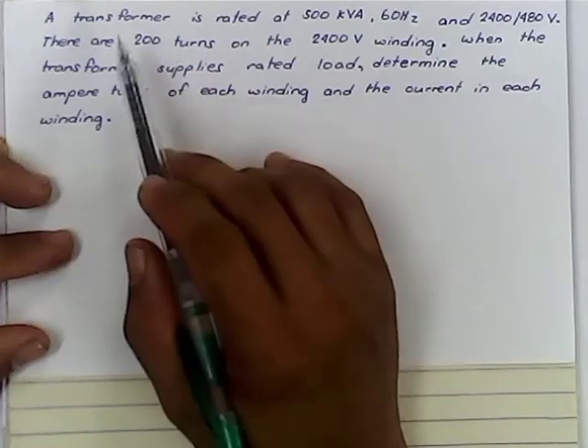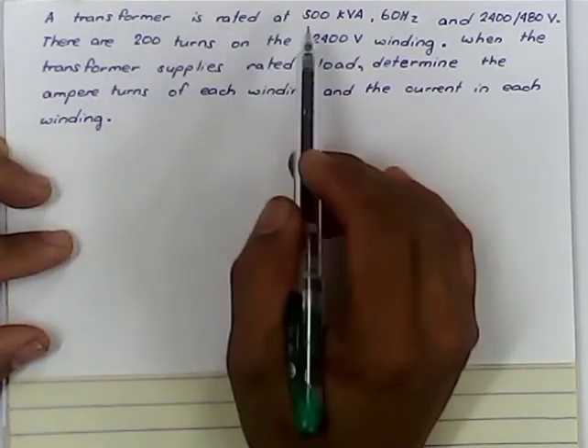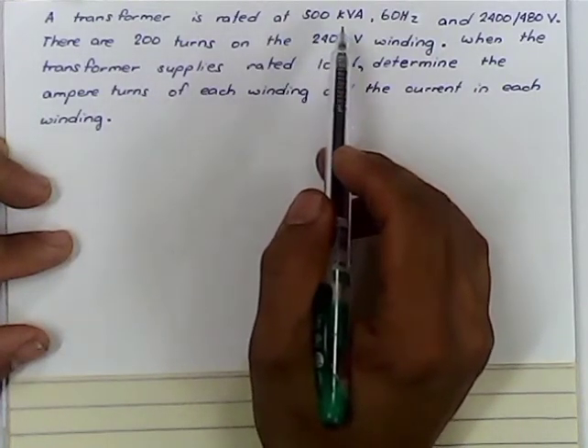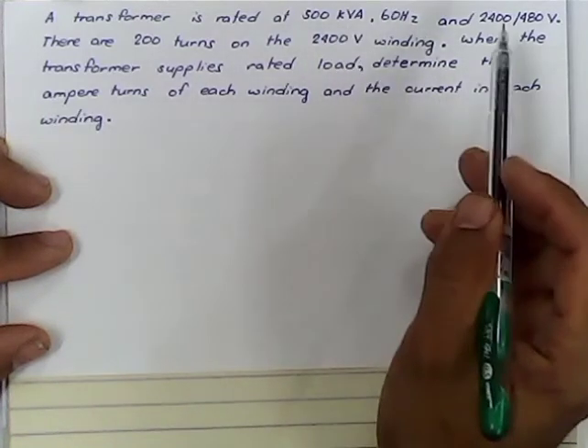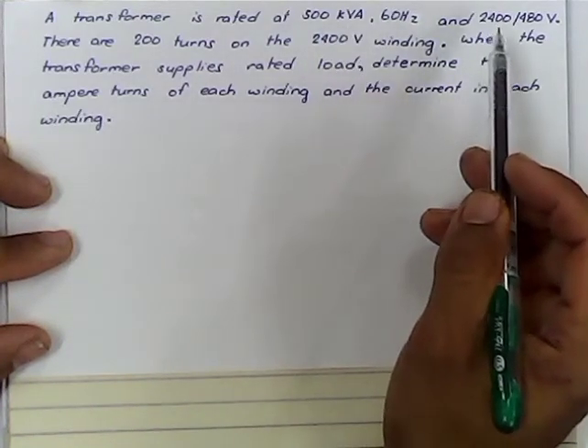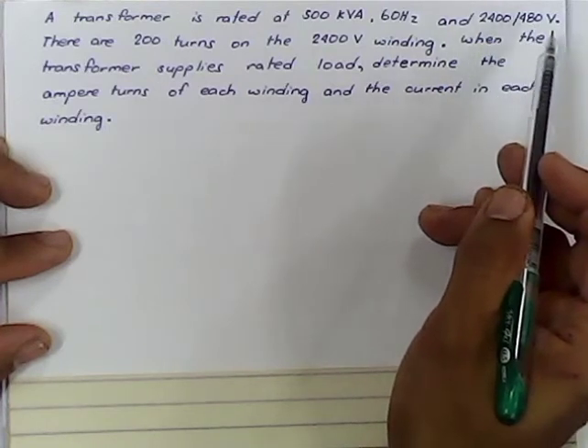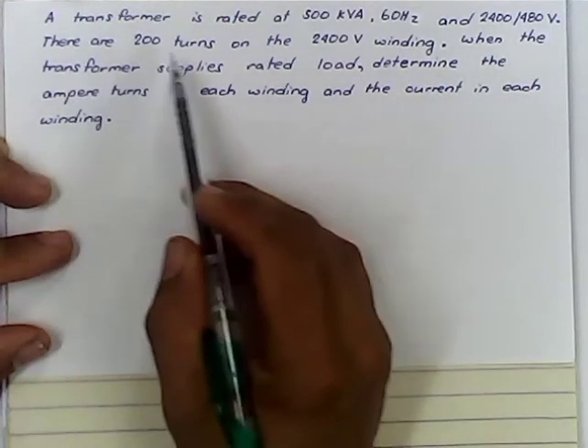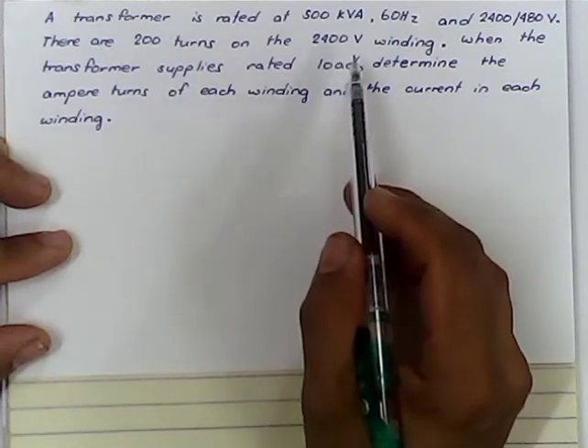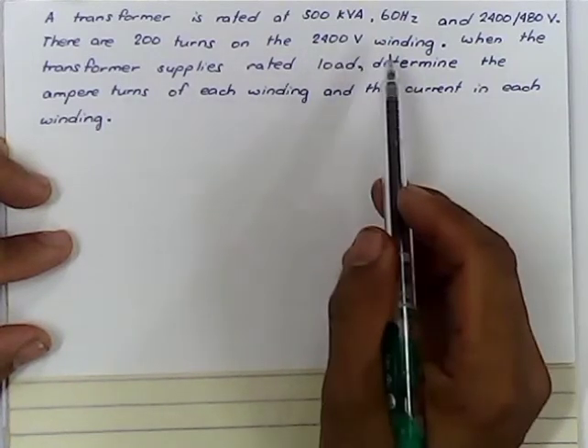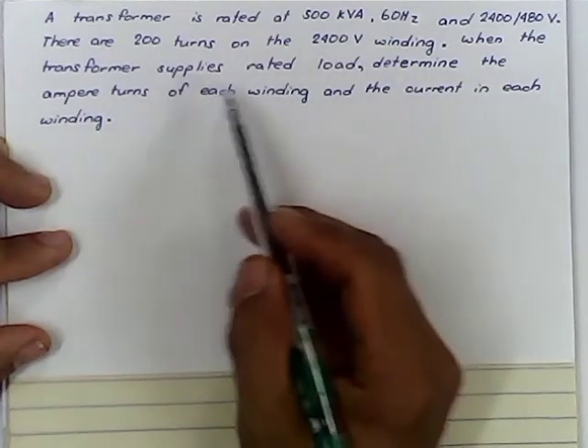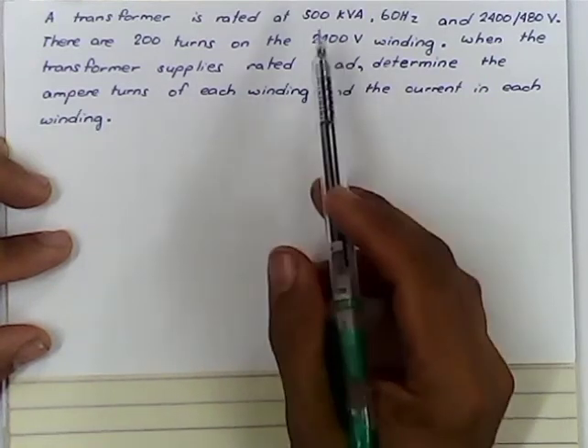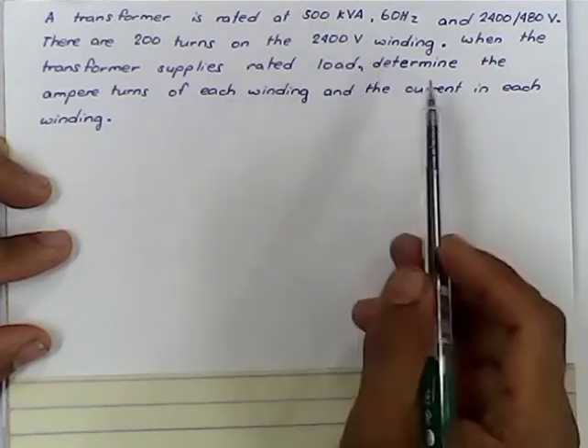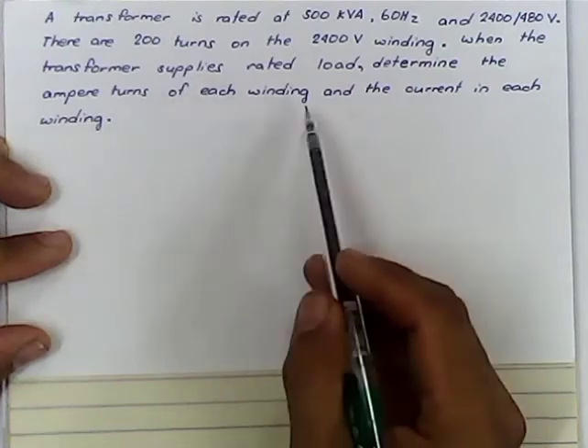Last problem, a transformer is rated at 500 kilovolt amperes, 60 hertz, and 2,400 volts para sa primary winding and 480 volts para sa secondary winding. There are 200 turns on the 2,400 volt winding, that is the primary winding. When the transformer supplies rated load, that is 500 kilovolt amperes, determine the ampere turns of each winding and the current in each winding.